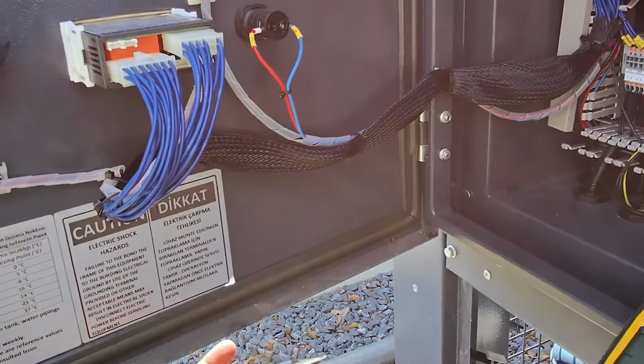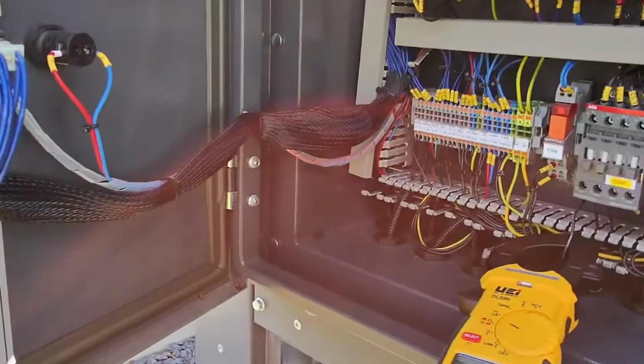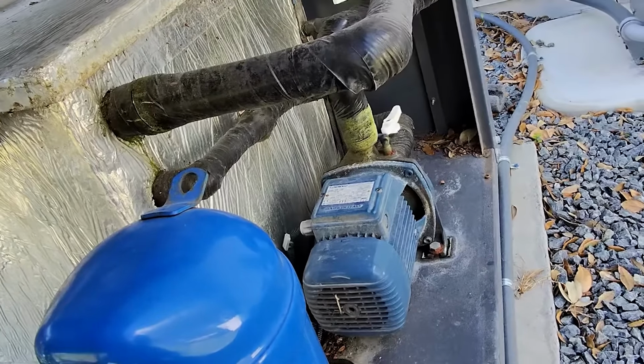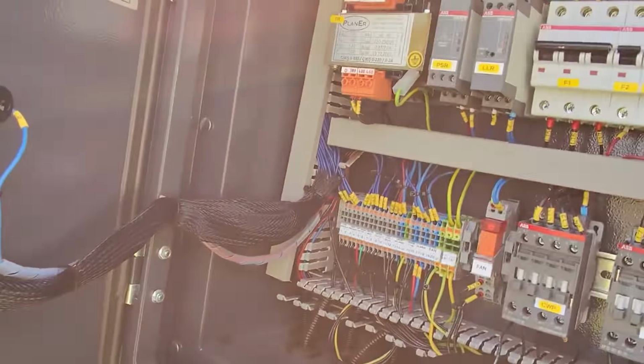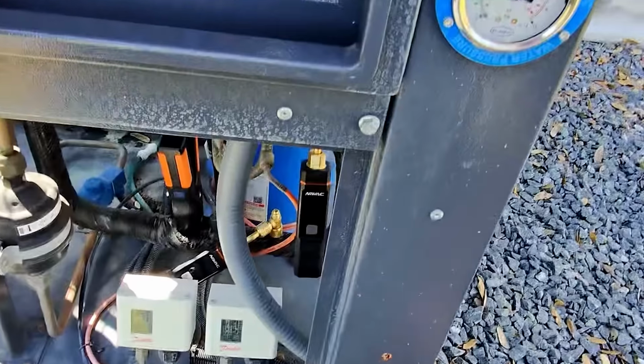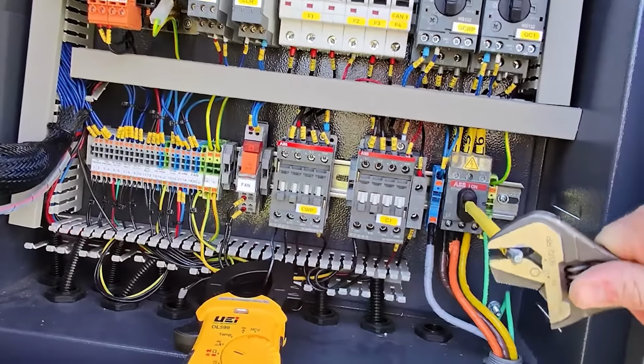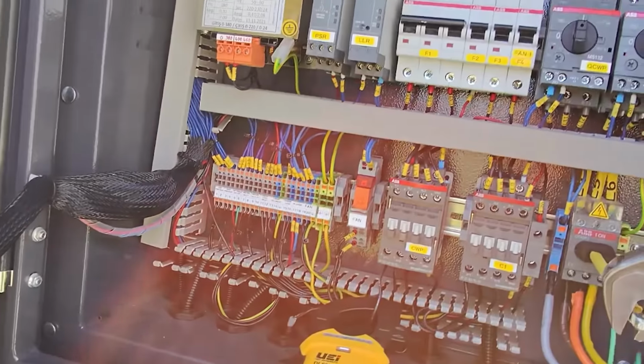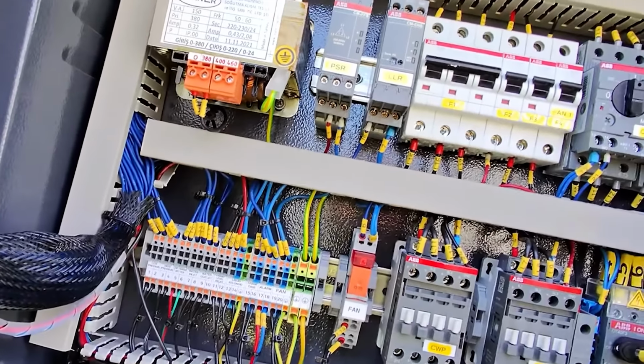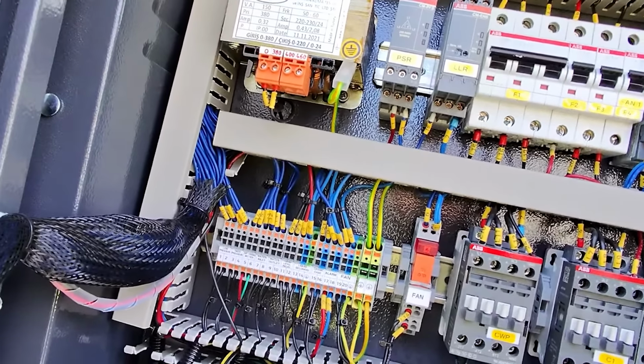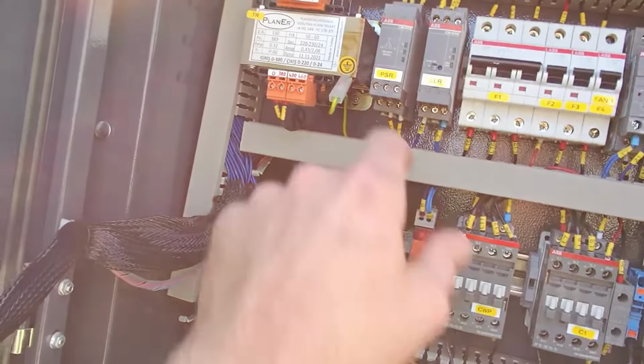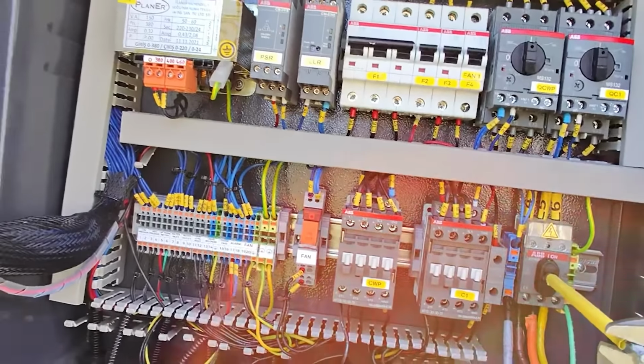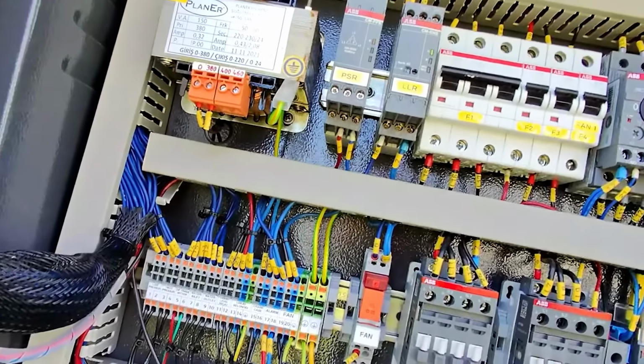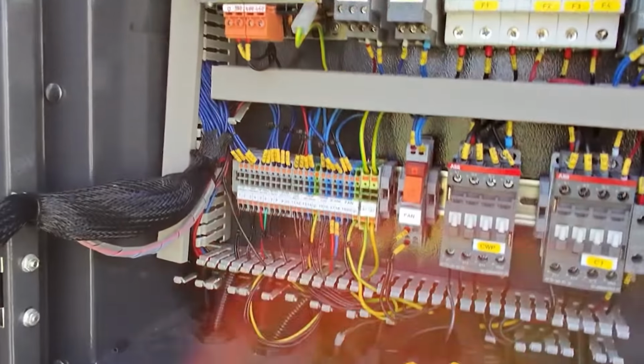So as you can tell, they've got a really amazing sound when it goes into alarm, but we're at 2.73 amps. Motor is rated for 2.5, so it is pulling elevated amps, but it looks like it's got a protection device. So we're gonna power cycle it with our trusty crescent wrench here. Although I do love the sound of that. Looks like it is adjustable on the range. So you've got your phase rotation protection there, and then it looks like our protection device, lock rotor. So let's see it in action again.